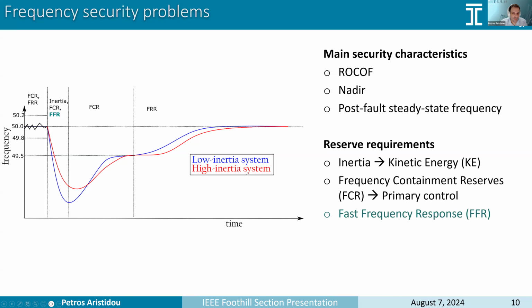If we talk in terms of reserves, so in terms of products, in the first area here, we have the inertia, which depends on the synchronous generators that we have connected, or if we have some sort of grid-forming batteries providing synthetic inertia. And then the primary frequency control in Europe is called the frequency containment reserves. So this is what impacts the nadir and the post-fault steady state. And in many countries, we're now introducing the so-called fast frequency response schemes, which operate again in this area here. They are very fast response schemes that introduce a certain amount of active power into the system. And the main reason for these is to handle the nadir over here.